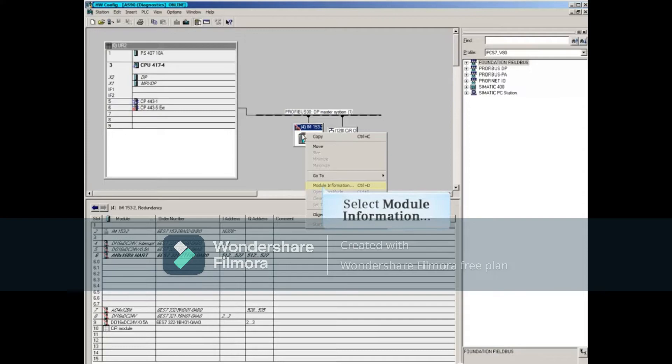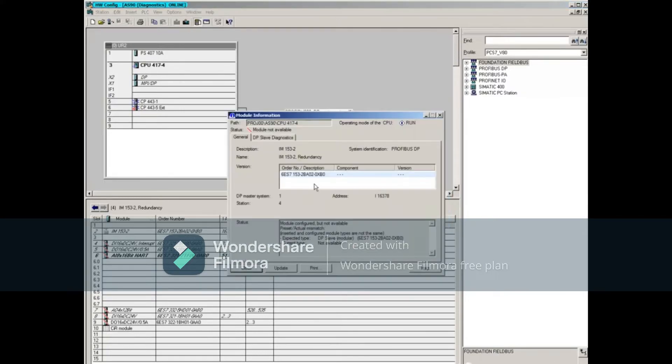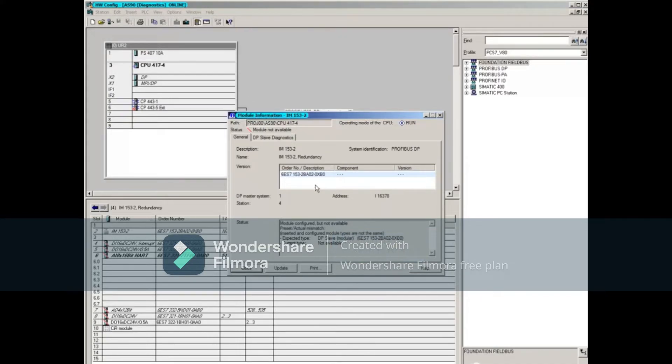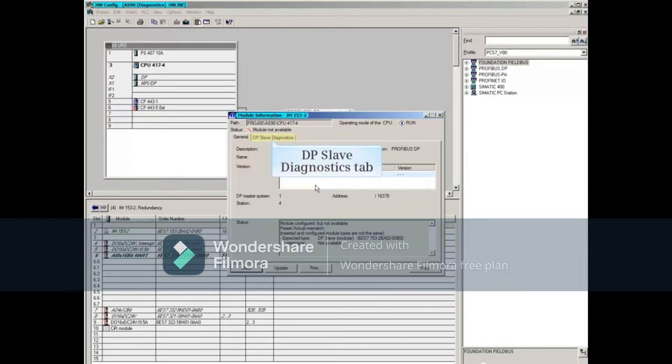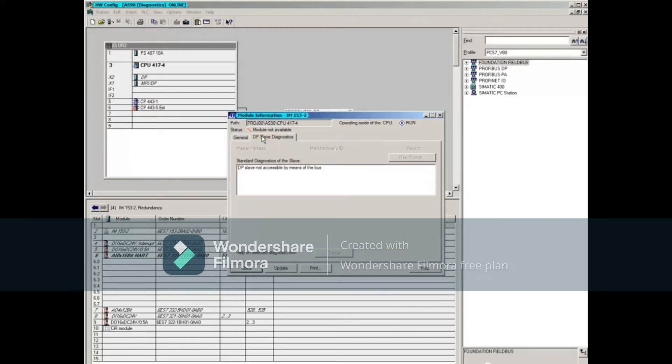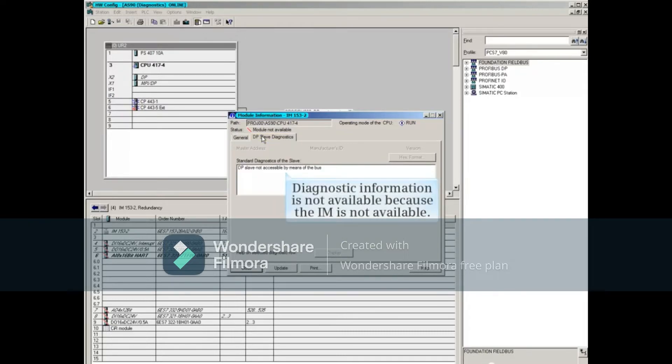Right-click the IM and open the Module Information window. Notice that the module isn't available. Click the DP Slave Diagnostic tab. Diagnostic information is not available because the IM is not available.